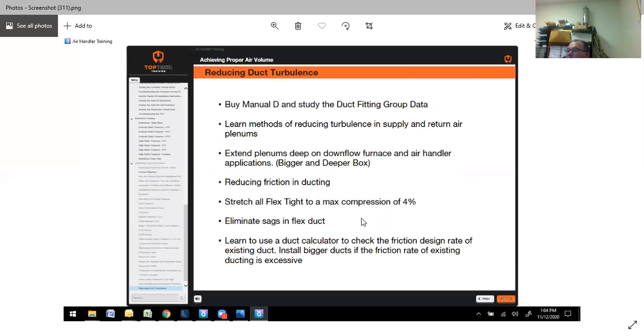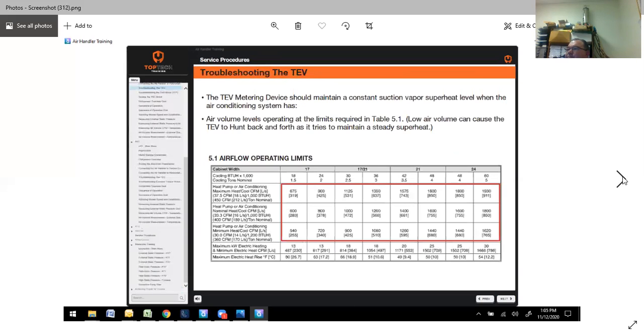I've seen lots of guys, if they're going to run 6-inch vents, but then they're going to do flex duct, well, run the same 6-inch vents. The flex duct is reduced, so you have to upsize that to accommodate exactly what airflow you're wanting to get.